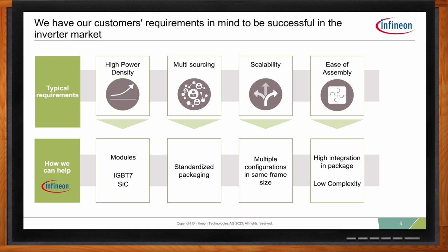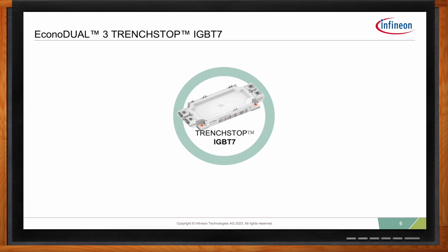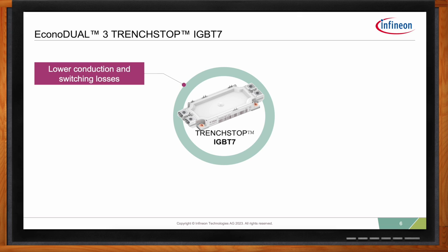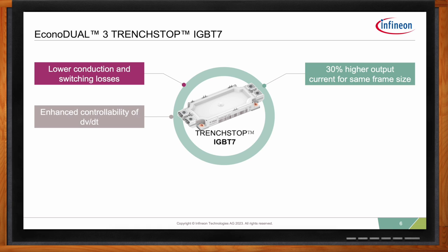Can you give some details about the Econo family and the IGBT 7 solution you mentioned? The EconoDual 3 module uses our latest IGBT 7 chipset, which reduces conduction and switching losses compared to an IGBT 4 chipset. In the same package, we can increase output current by about 30 percent. We also have enhanced controllability of dV/dt with this package.